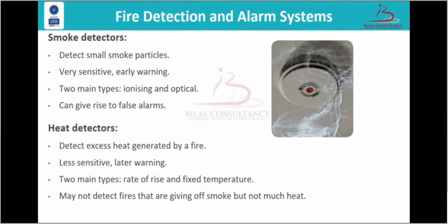Smoke detectors are very common and they detect small smoke particles. They are usually very sensitive and give early warning. They are of two main types, ionizing and optical. They can give rise to false alarms if used in a humid, wet, dusty or smoke-filled atmosphere. Heat detectors are more suitable for certain applications. They detect the excess heat generated by fire and they are usually less sensitive and give later warning. They come in two main types, rate of rise and fixed temperature. They may not detect smoldering fires that are giving off smoke but not much heat.